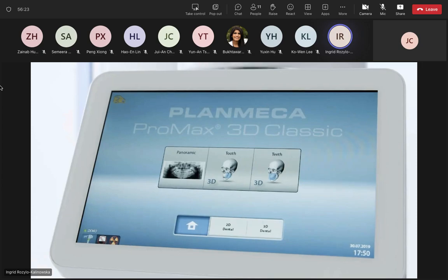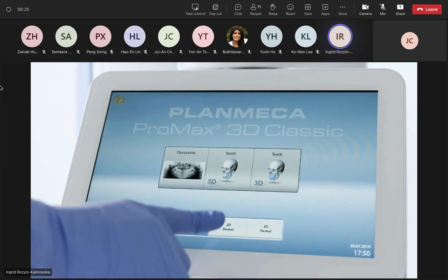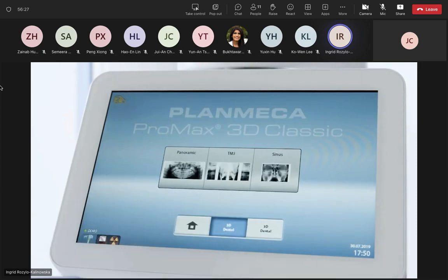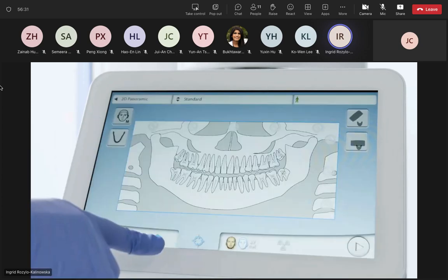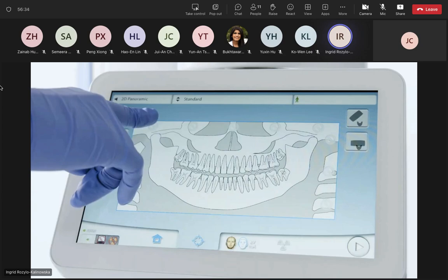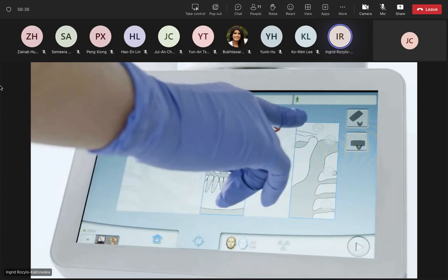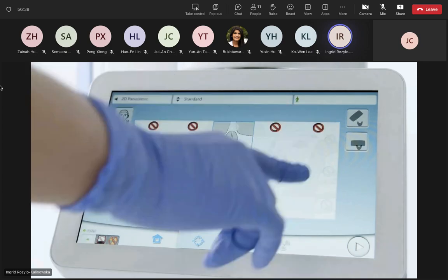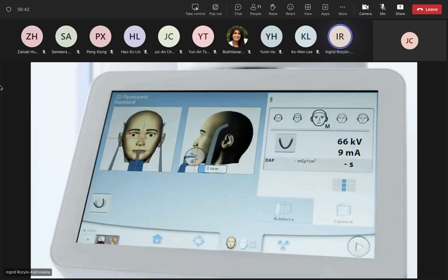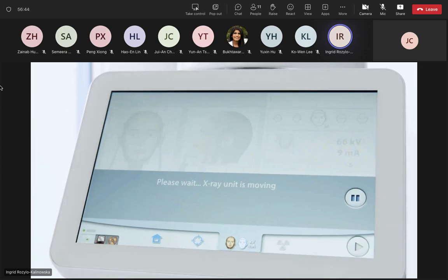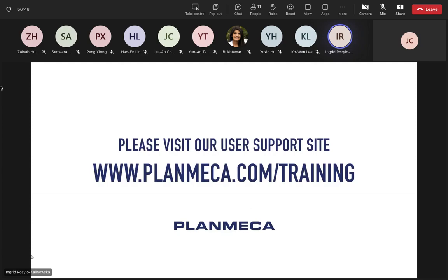Periapical setup. To capture a segment PA-like view, select 2D dental, then panoramic from the touchpad of your ProMax X-ray unit. To isolate the desired region of interest, select the radiation symbols. Press forward in the lower right of the touchpad to continue. Follow the rest of panoramic positioning instructions. For information on add or...